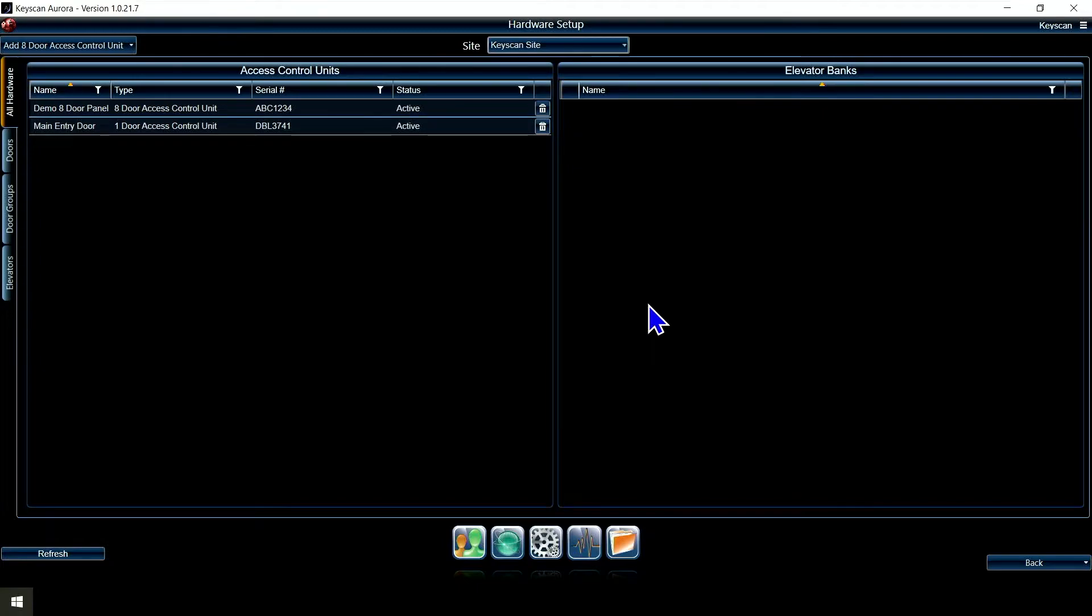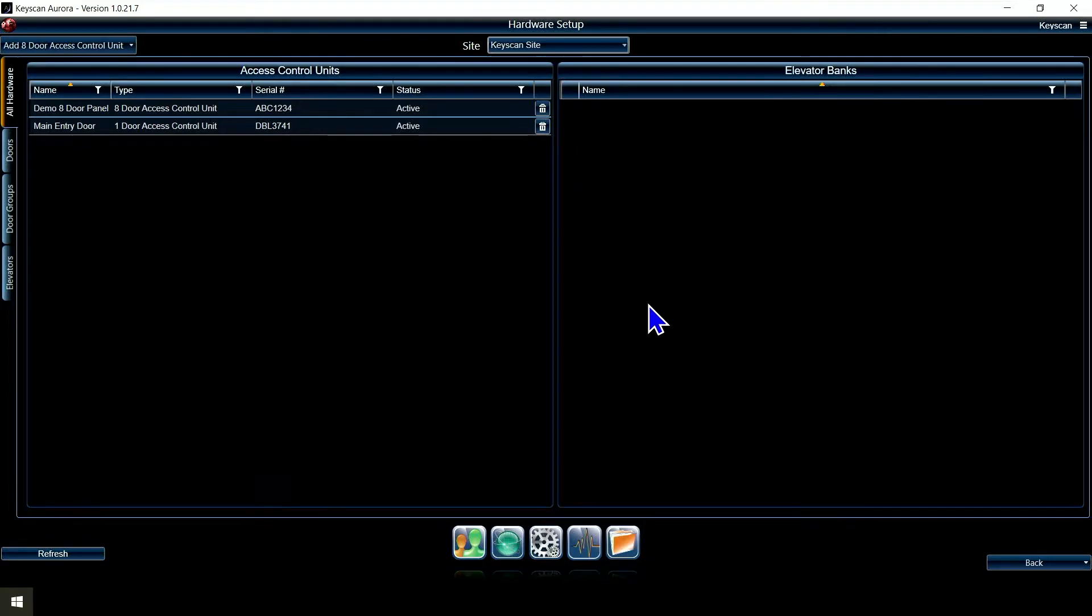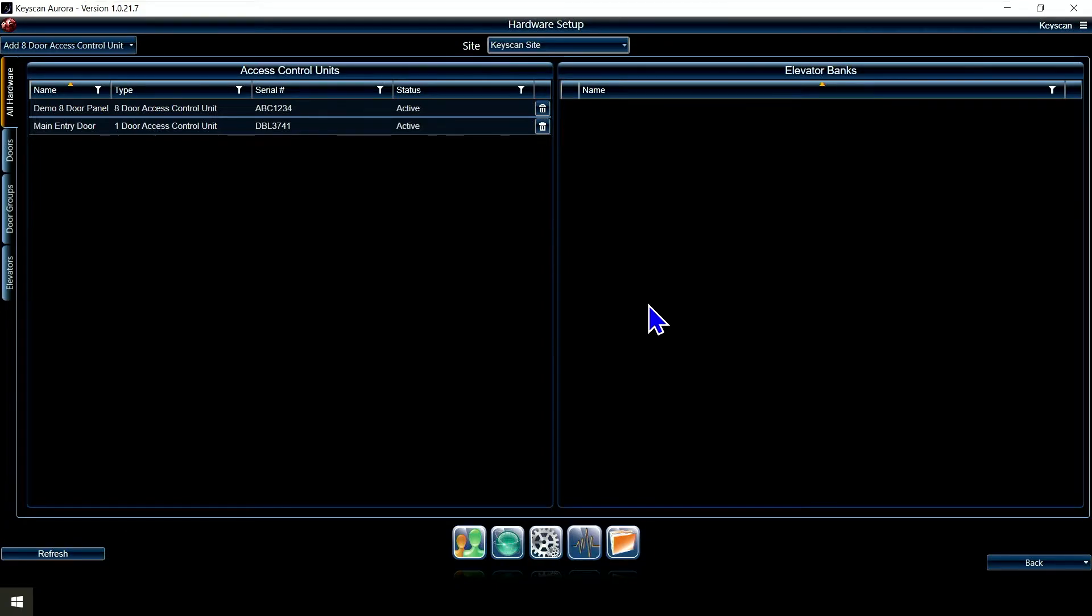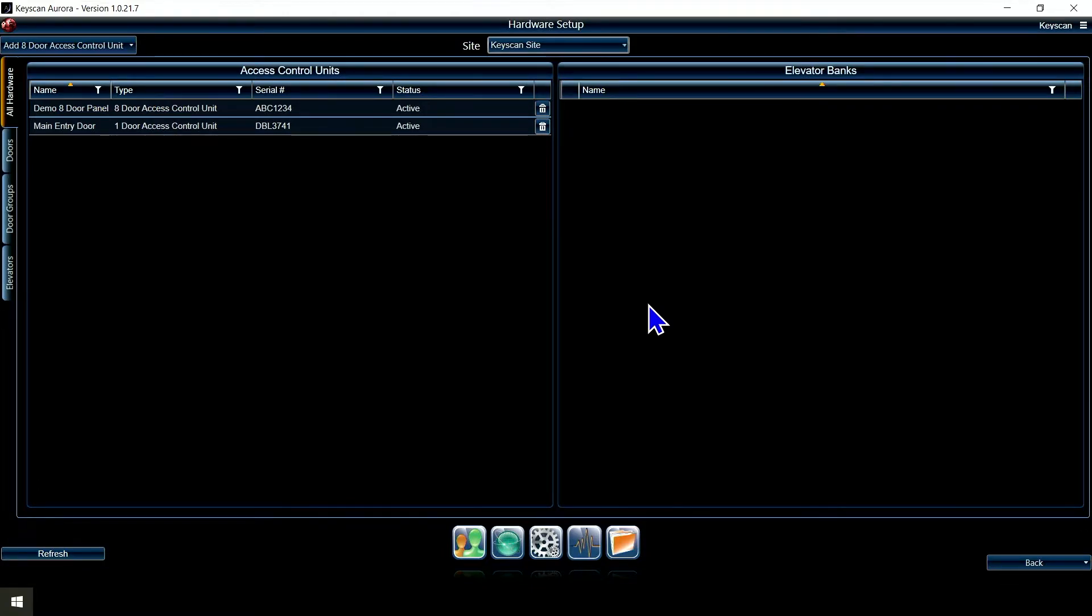There's a couple ways to do it. If you're using a NetCom 2P or the CA-150 network port, you can actually take a computer, put it on the same network as that panel with the same default setup. I believe the default IP address in those is 192.168.100.100, I think, but verify that on your paperwork.